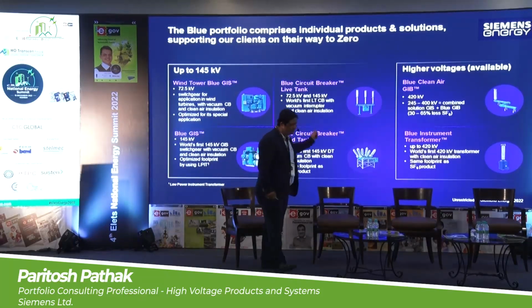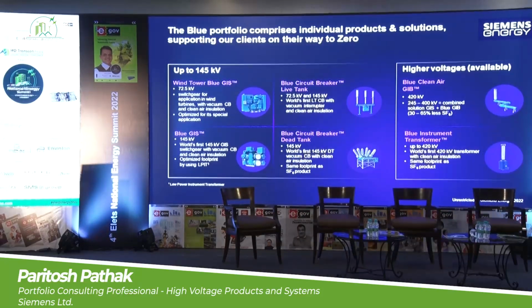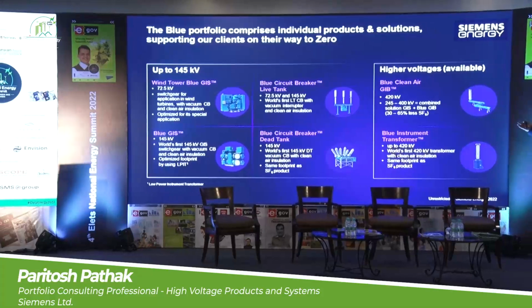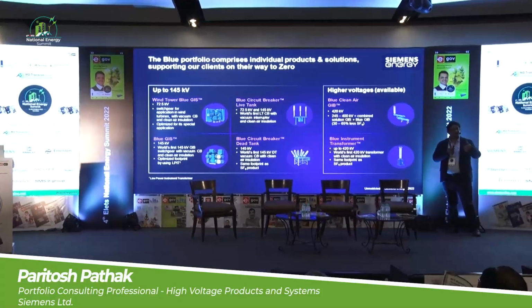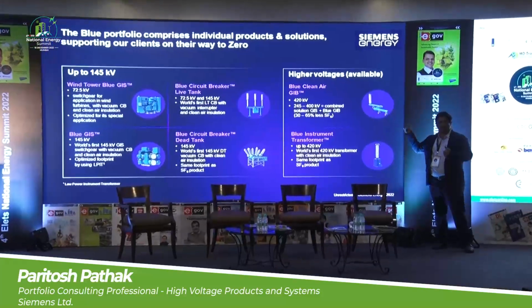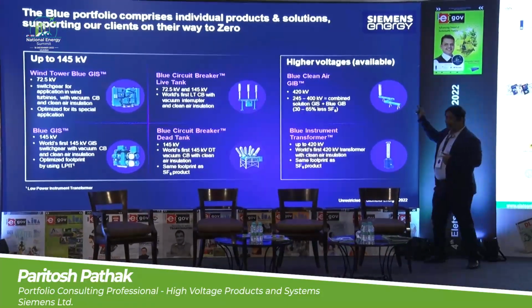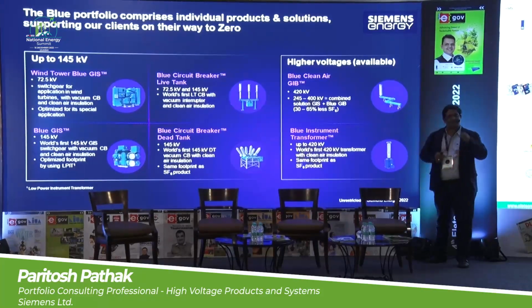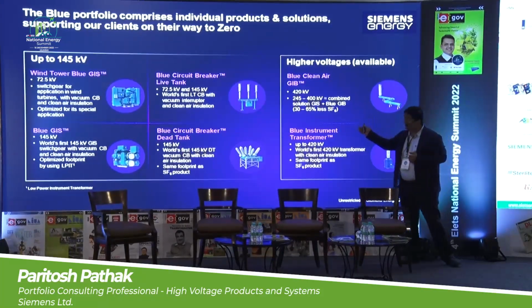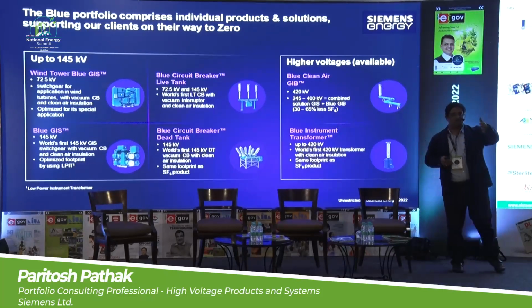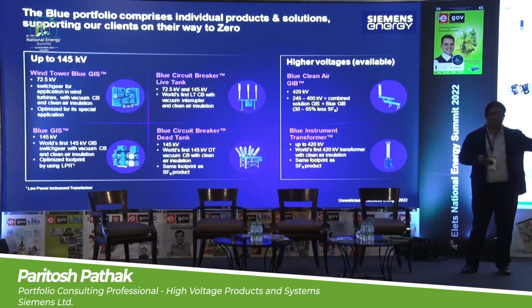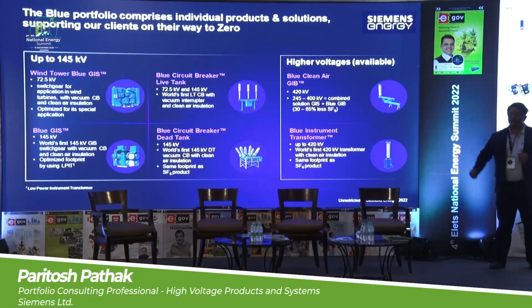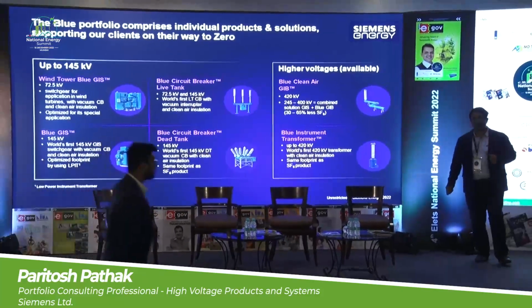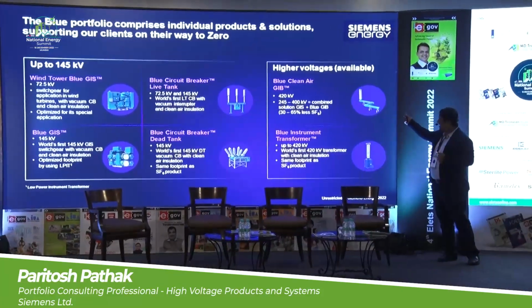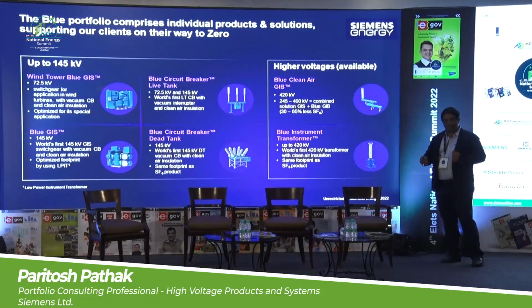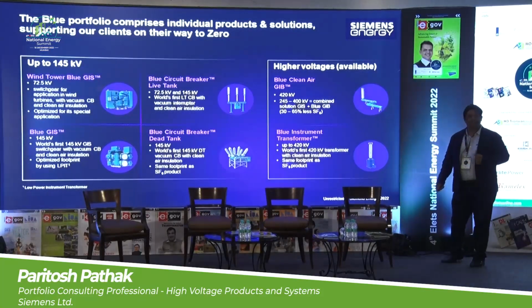So far we have seen switching components; now we move to non-switching components. The bus duct is a very important aspect here — we can combine SF6 insulated switchgear with clean air insulated bus duct. Even with this implementation, we can practically achieve a reduction of 30 to 65% less SF6 gas. If we talk about transmission utilities like MSETCL, PGCIL, GETCO, or any other, they use 2, 3, 4 kilometers of SF6 bus ducts, and we can reduce this quantity with the solution available today. This is an aspect that needs to be looked upon.